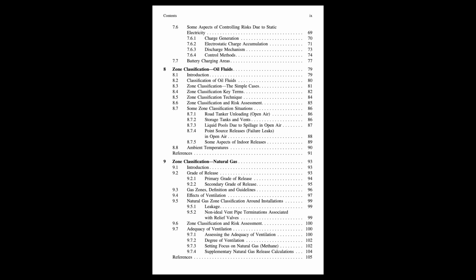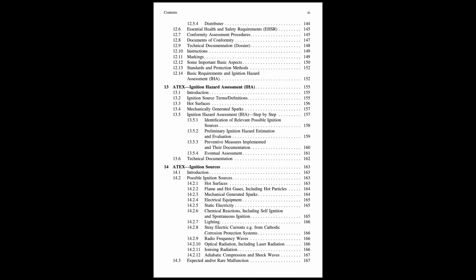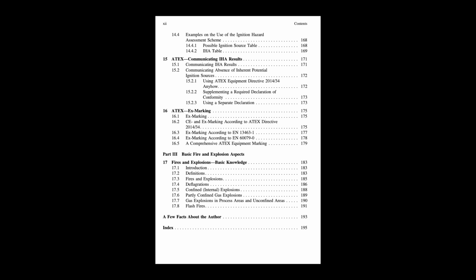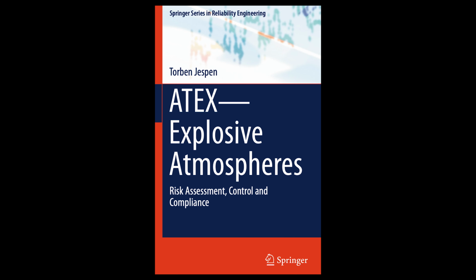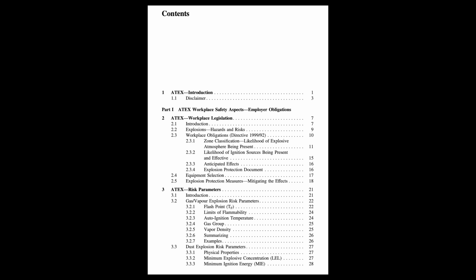Simple but powerful. And our source gives a very specific definition of an explosive atmosphere. It's not just any flammable stuff floating around. No, the definition is quite precise. It's a mixture of flammable substances, could be gases, vapors, mists, even certain types of dust, mixed with air, but only under specific atmospheric conditions. If those conditions are met and you introduce an ignition source, then the combustion can spread really rapidly through the entire unburned mixture. That's the explosion. And what are these atmospheric conditions? According to the guide, we're generally talking about a pressure range of about 0.8 up to 1.1 bar absolute, near normal atmospheric pressure, and a temperature range usually between minus 20 degrees Celsius and plus 60 degrees Celsius. If things are way outside that window, the specific ATEX rules we're digging into here generally don't apply directly. Other safety measures might, but not these specific ones.